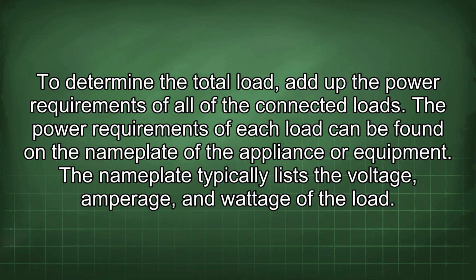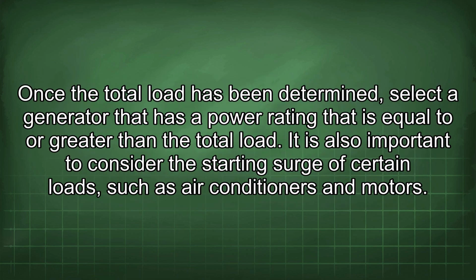To determine the total load, add up the power requirements of all of the connected loads. The power requirements of each load can be found on the nameplate of the appliance or equipment. The nameplate typically lists the voltage, amperage, and wattage of the load. Once the total load has been determined, select a generator that has a power rating that is equal to or greater than the total load.